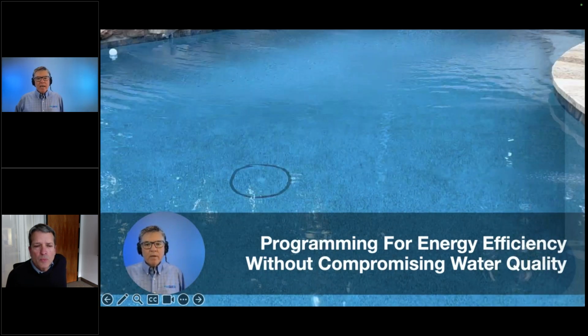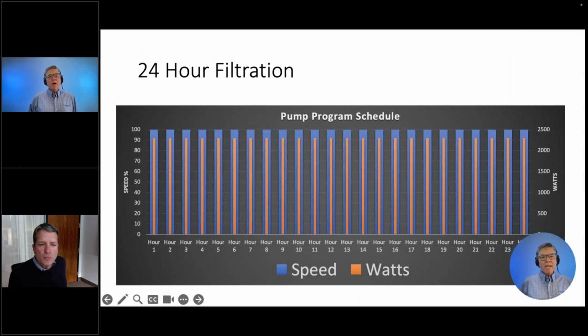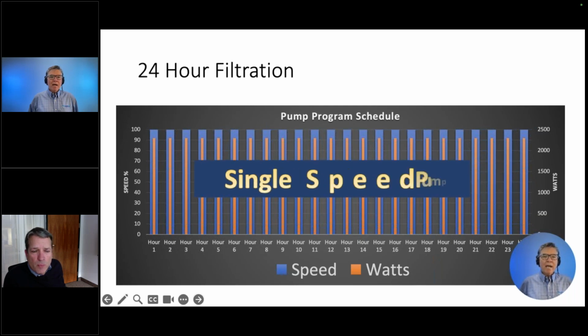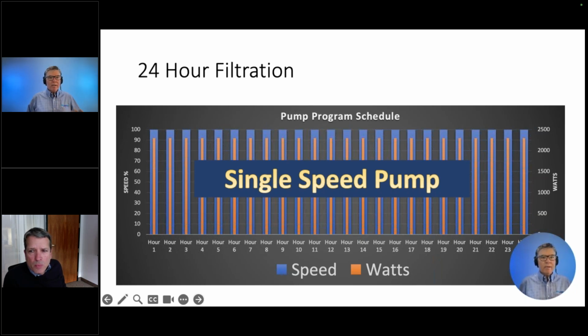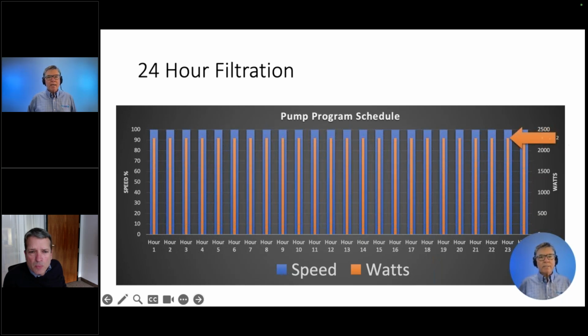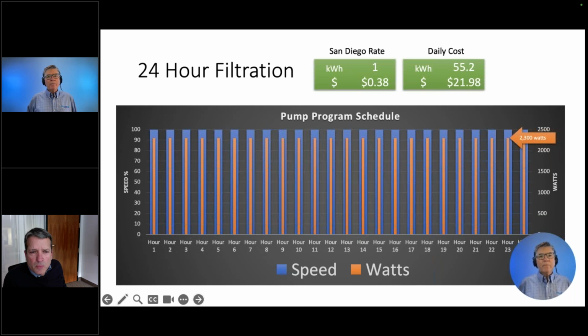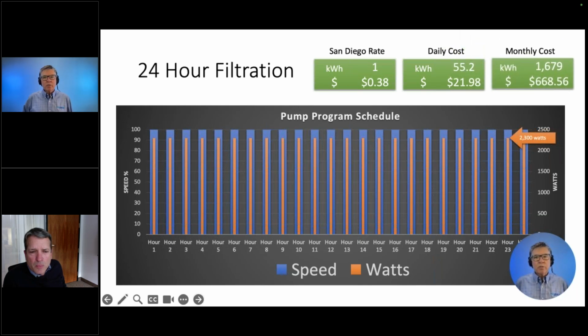Now, for the last bit, I wanted to apply this concept so you can see how it can be valuable to show a return on investment for your time to program, learn, and educate yourself, to separate yourself. If we look at the single speed pump, this is that same 3 horsepower pump, but on a public pool running full speed. It's going to operate 24 hours a day at 2,300 watts. This happens to be California, the San Diego rate of 38 cents. That would be 55 kilowatt hours, $22 a day, or nearly $700 a month. So homeowners would pitch a fit. So we don't do this, right?